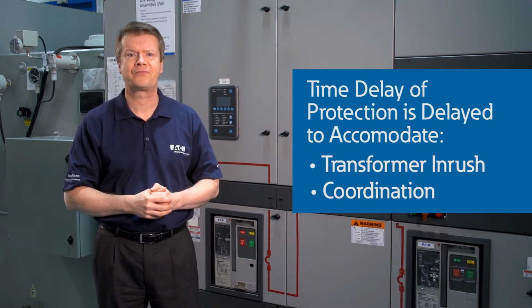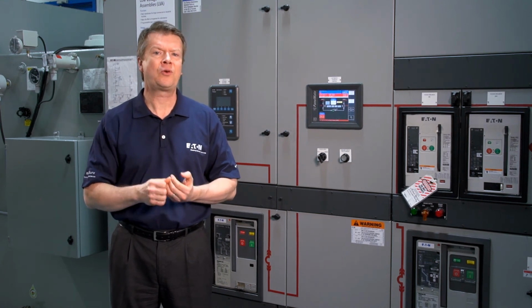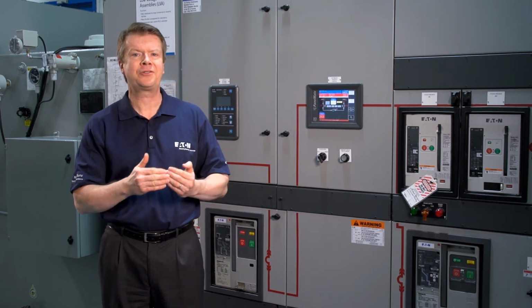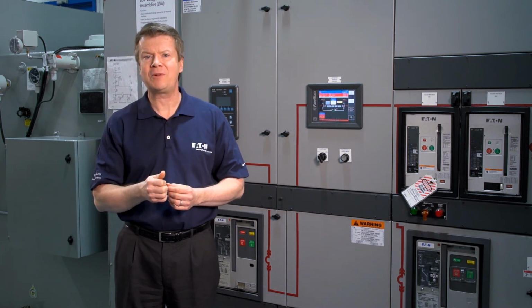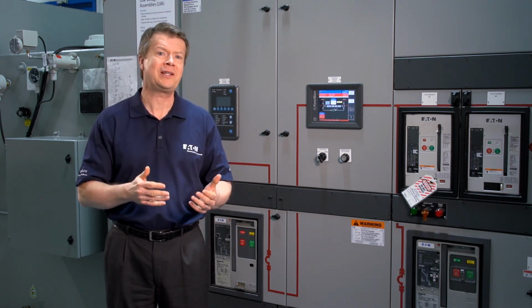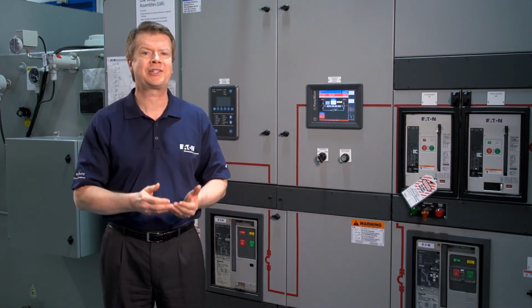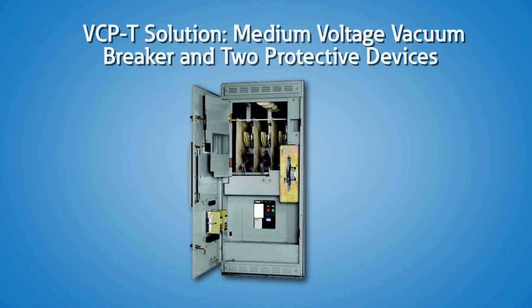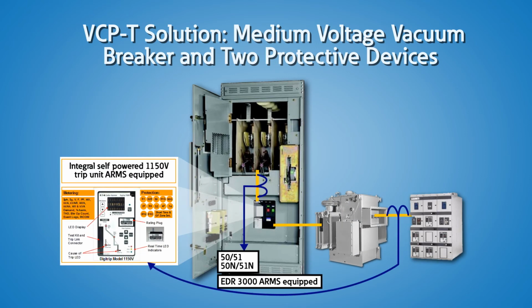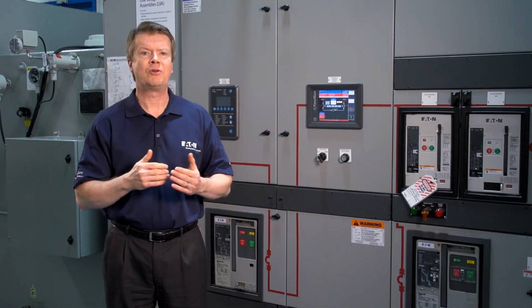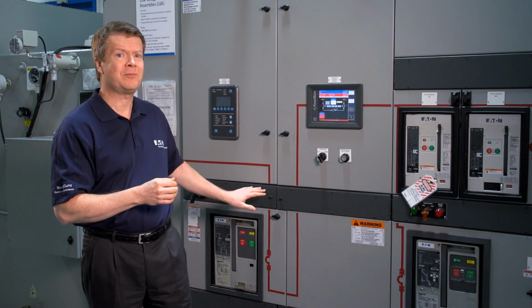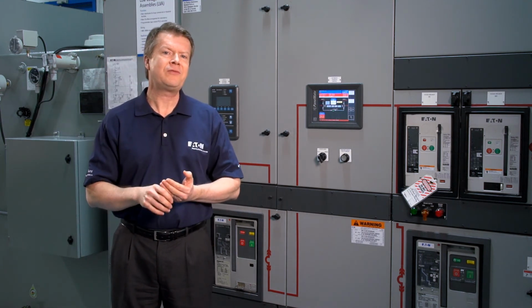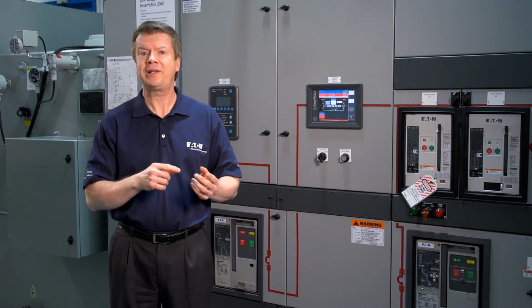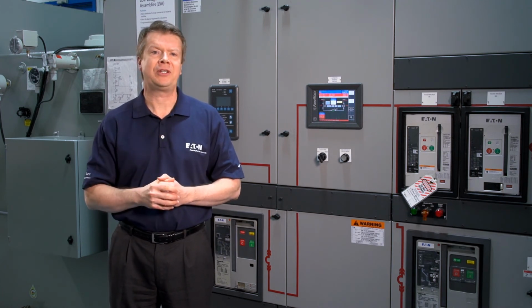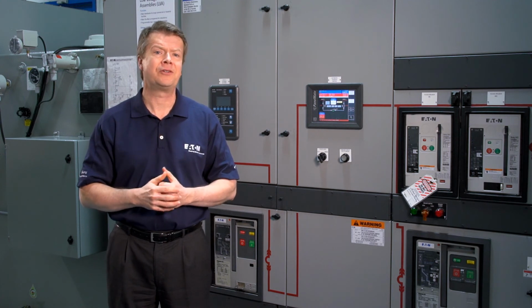So how could we create a selectively coordinated system that compensates for the expected transformer inrush, but at the same time clears a fault on the line side of this main breaker quickly enough so that the arc flash energy levels are substantially lowered? Our VCPT solution allows us to use a medium voltage vacuum breaker and 2 protective devices to detect faults in different zones around this transformer. The most difficult fault location being the line side of this main breaker. With this solution, this medium voltage breaker can selectively determine how quickly to clear a fault, significantly reducing the arc flash energy to well below 10 calories during maintenance conditions.